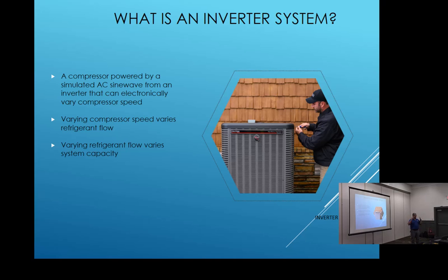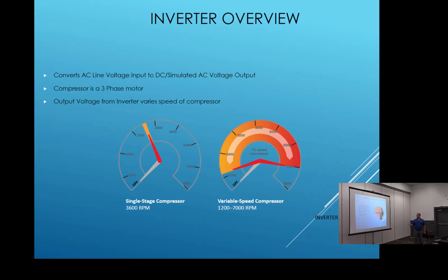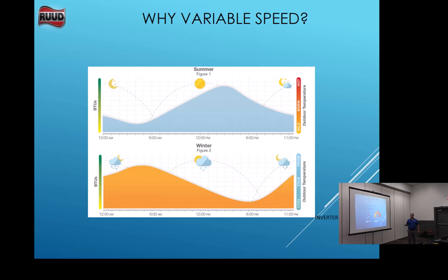Varying compressor speeds varies the refrigerant flow, and varying refrigerant flow varies system capacity. So we talked about that single stage compressor runs at 3,600 RPM, and this variable speed will run from 1,200 to 7,000 RPM. And we're going to look at why variable speed in a typical summer day, but our winter is down here also, right? Okay. We have low temperatures in the evening, and as we come up in the morning, the temperature in the summertime comes up, peaks during the day, and then goes back down.